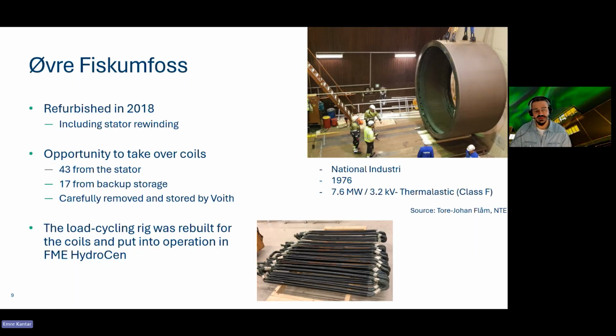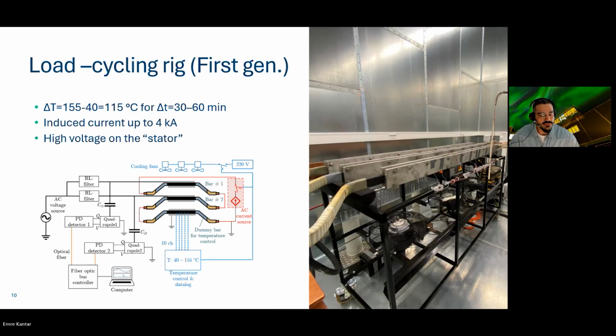The results that I will show today are from coils taken from a plant that was refurbished back in 2018. We got some coils from them, adapted them in our test rig and exposed them to accelerated aging. The first generation of the setup looked something like this, where we mimicked the stator core by using steel plates and confined the bars between them, which also mimics the mechanical aspect. But this is only a single-phase setup, as a good start.